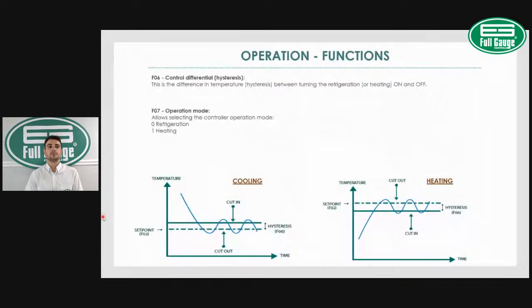Now, operation. We understand that this controller has the capability of controlling cooling and heating. How do you set that? Function F07. When you access your controller by pushing up and down, we have the functions. We go to function F07. Here we go. So if F07 is set to 0, the controller works in the refrigeration mode. If you change this to 1, the controller works in the heating mode. The controller comes preset to refrigeration, and in this case we're going to leave it in refrigeration.